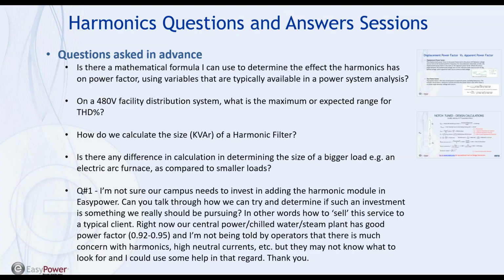When you have many small loads on a facility, those small loads have varying phase angles. You have more cancellation. So the impact of the small harmonic producing loads is not of concern as much as those large loads. So if you have a 1,000 horsepower or 2, 3, 4, 5,000 horsepower VFD drive, you must certainly model that and be more concerned about the impact of the harmonics related to that device, because the true output of that device will be what your facility sees. When it's a bunch of small devices, although they could add coincidentally, they can all be in phase with each other and they can all add, it tends to be that they don't add directly. So the impact of the many small loads is much less than the impact of one large load.